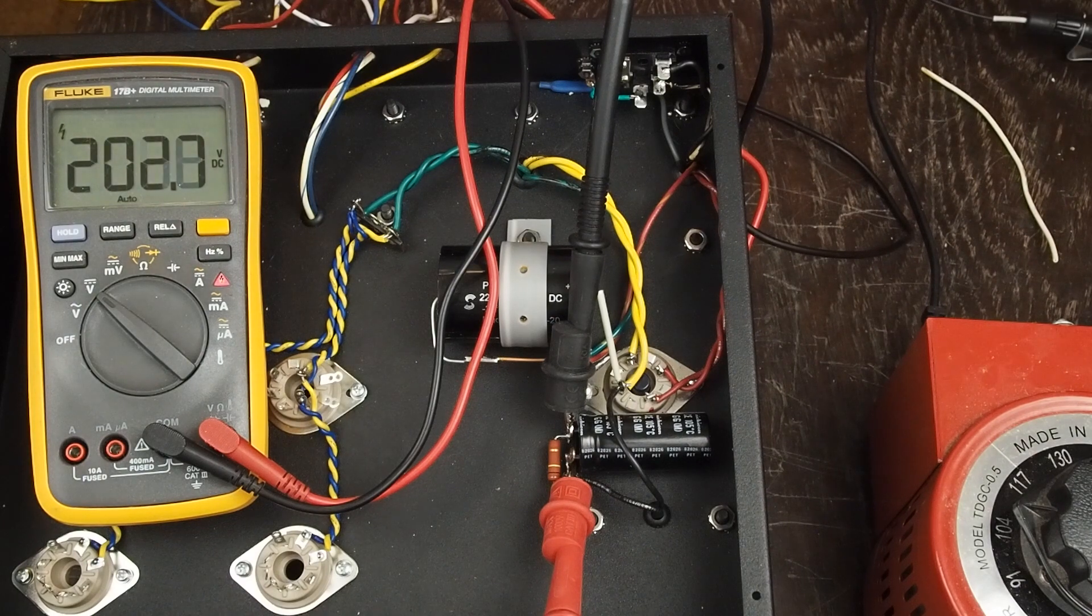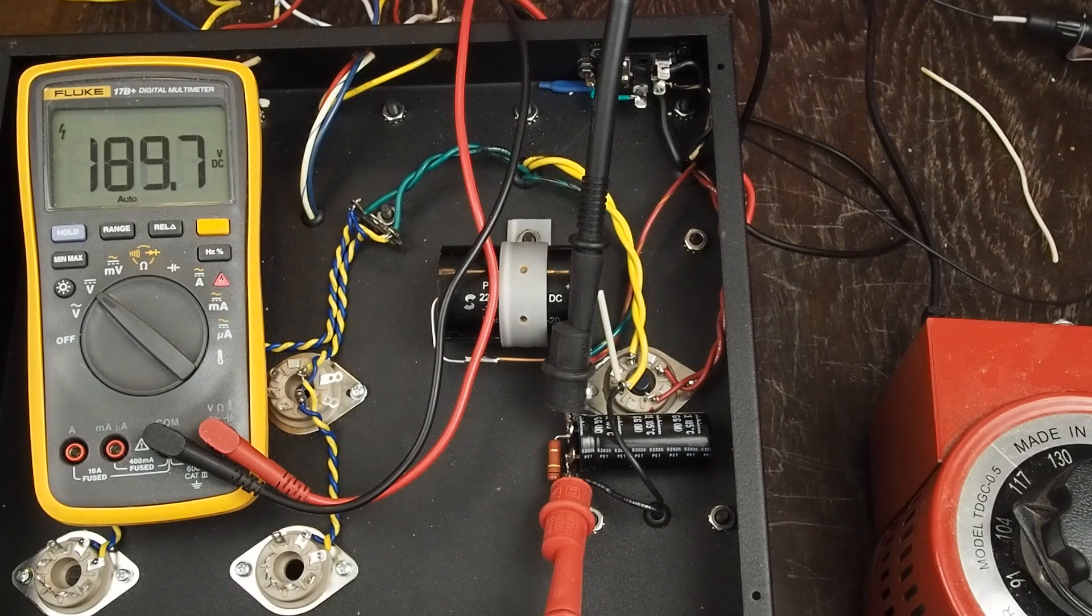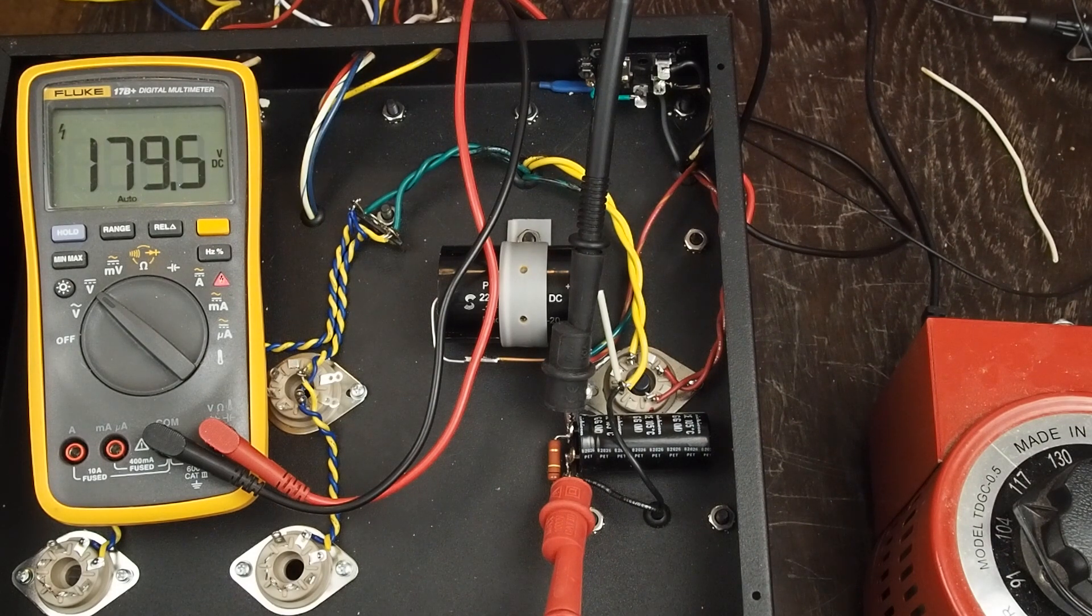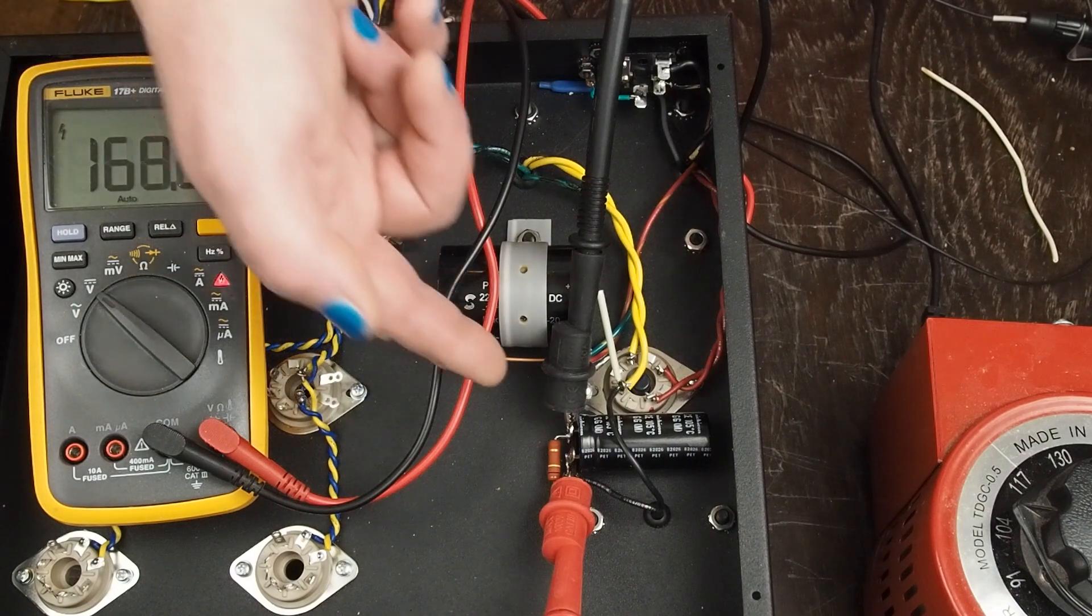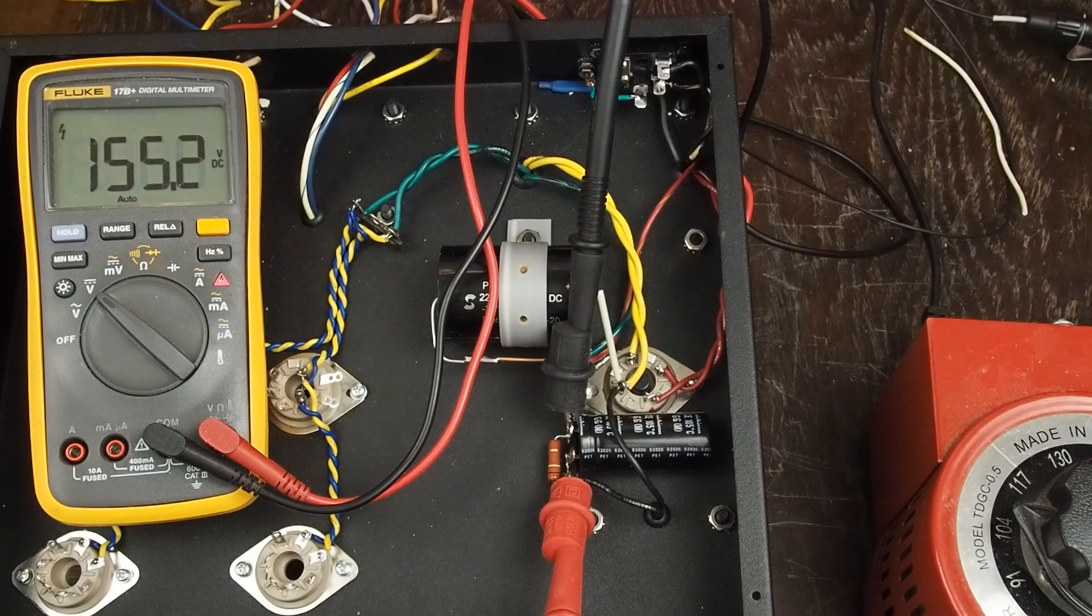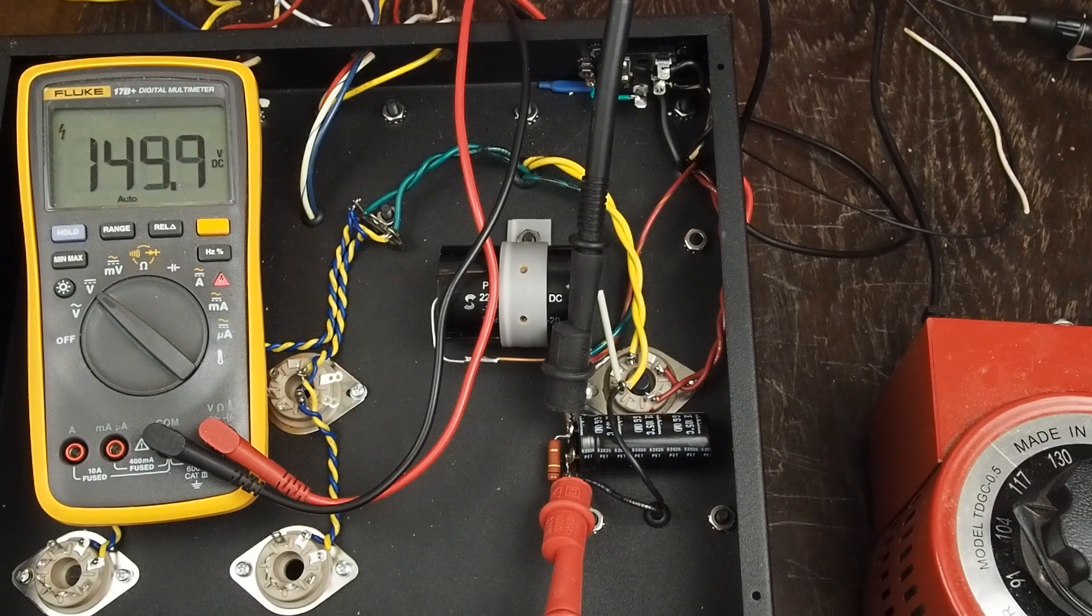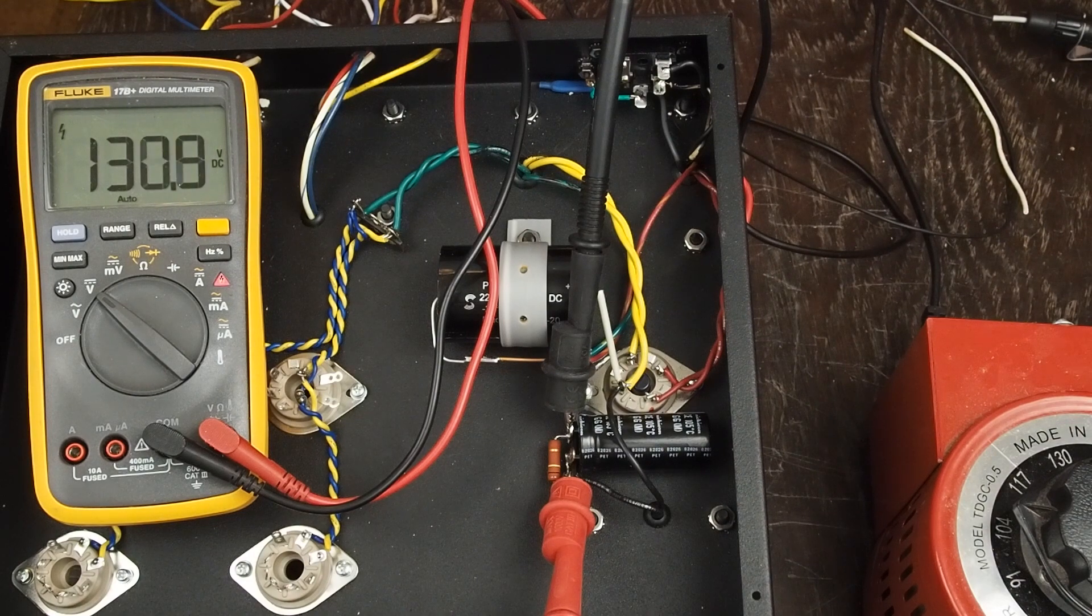So again, be careful guys. Understand that these things are dangerous to work on if you're not paying attention. This is also showing you the value of having this bleeder resistor in here that we put down here, that without that it would still be sitting up over 400 volts and it might take 45 minutes or an hour for the voltage to come down to a safe level.